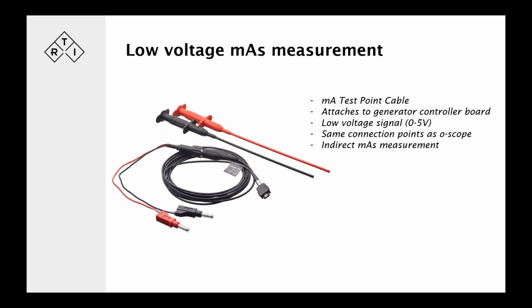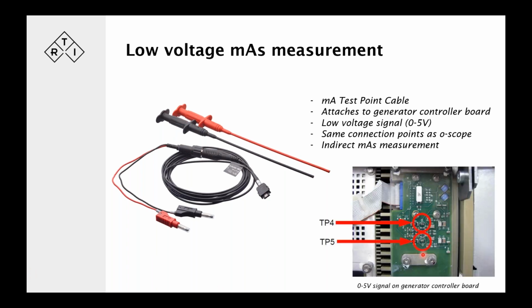We talked about the mA test point cable earlier. This is what it looks like. It's a cable here that attaches to the Piranha or Cobia, and to that cable we've got some lab connectors, which can then be connected to, for instance, these tweezers or clamps that you clamp on to the generator controller board. For instance, this is one example like this, where you have test points where you usually attach the oscilloscope. So here, if you can attach these to one of the test points and chassis ground, you'll be able to measure an indirect mA measurement. You're measuring a voltage signal, 0 to 5 volt typically, which then scales to the actual mA signal. So that's a convenient way of capturing that value.